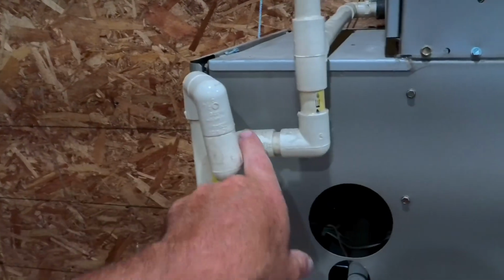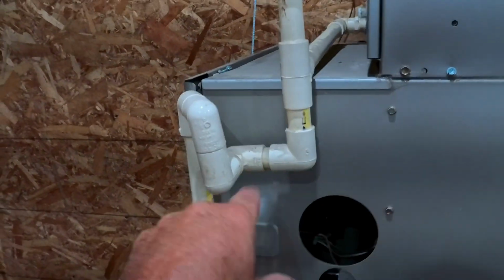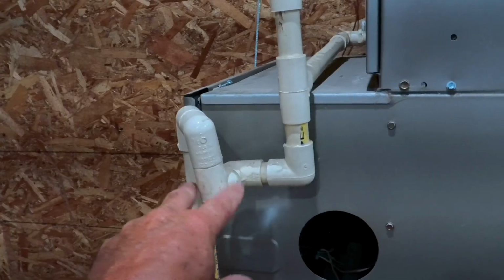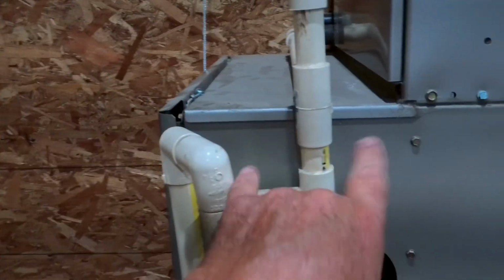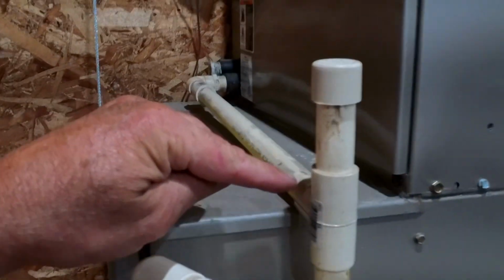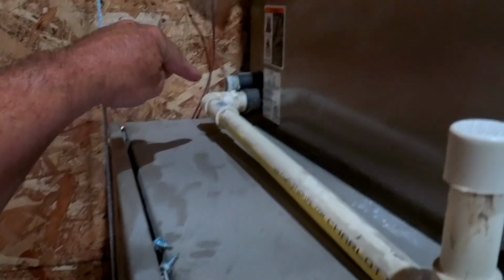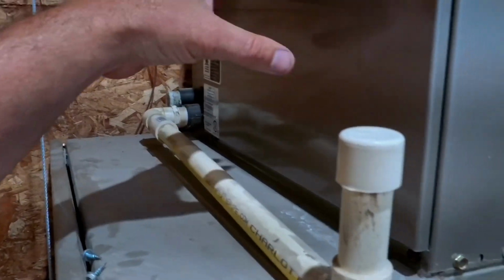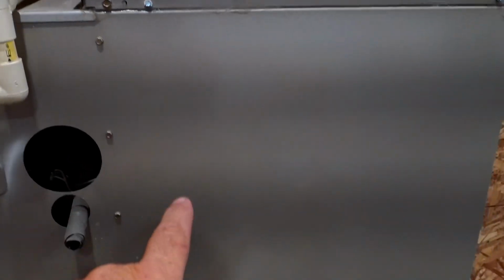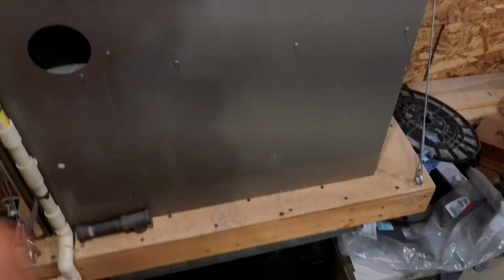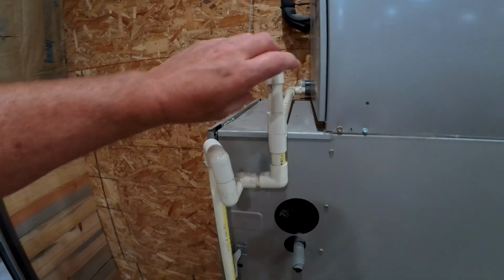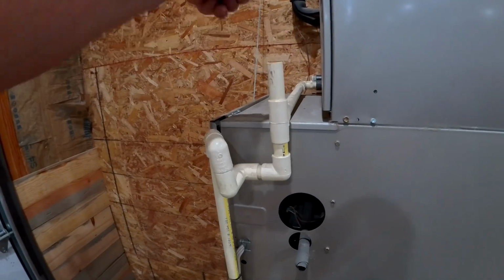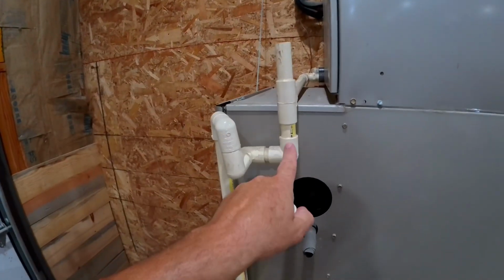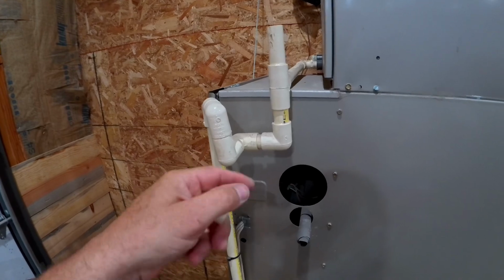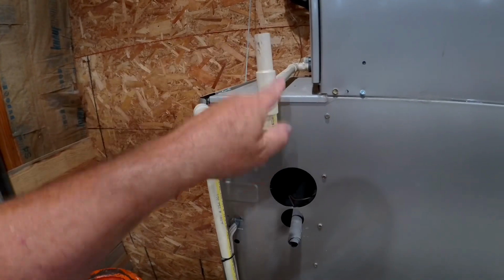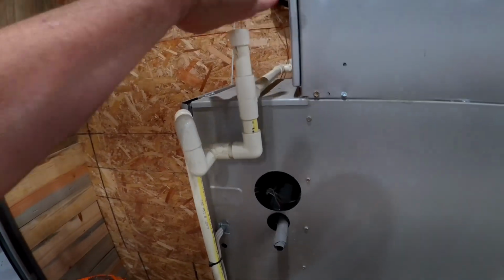The condensation trap in this situation is the most common area for a backup to start. By this being plugged with gunk internally, it allows the water to back up all the way back into the A-coil and then overflow internally, which obviously is going to run down through the furnace and out the bottom of the furnace itself. So as you can see on my system, I installed a clean out cap right here at the top of the trap. That way if this does get filled up with crap, I can simply pull this cap off, flush the system out, put the cap back on, and it's good to go.